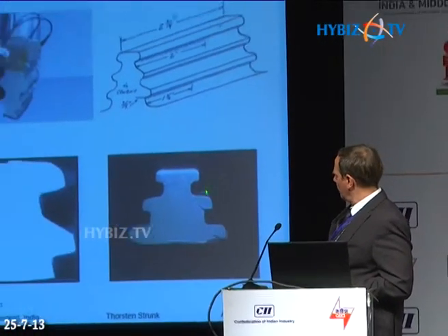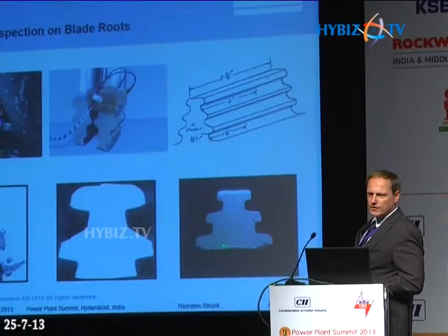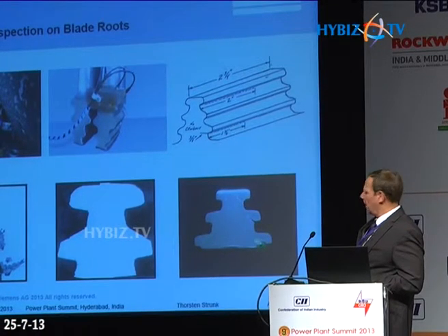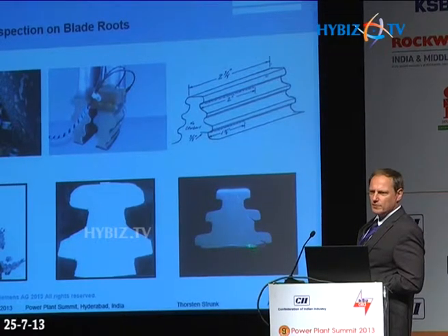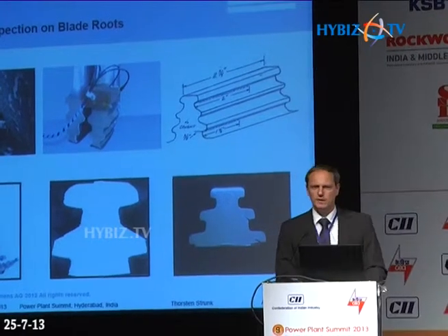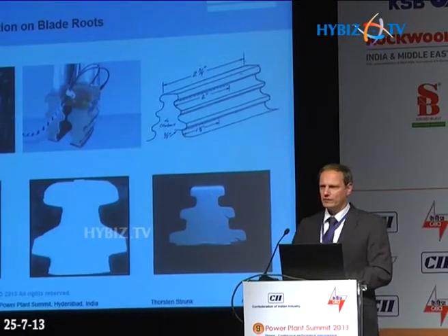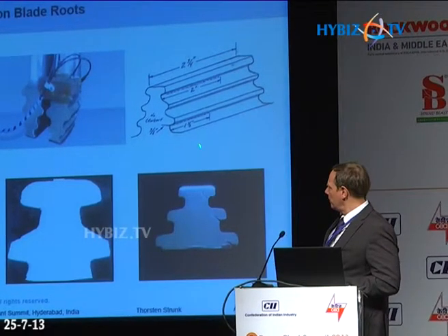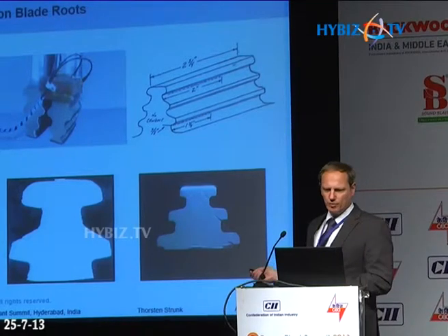And if you would not do anything, as you can see here in this picture, these cracks propagate a lot more. And if you don't do anything, the likelihood that those give way and your blade comes out of your turbine is pretty high. So you have to do something in order to make sure that you have safe operation.